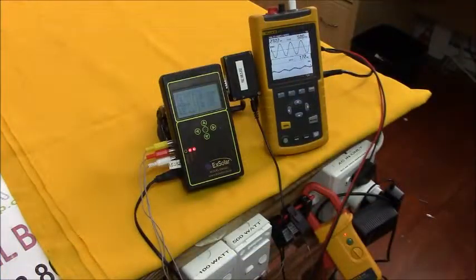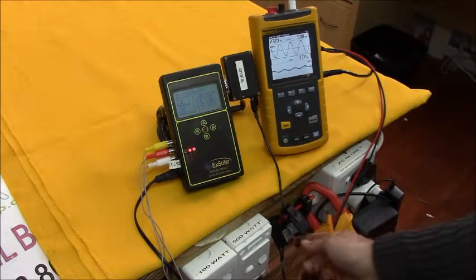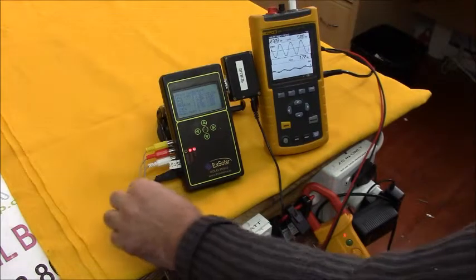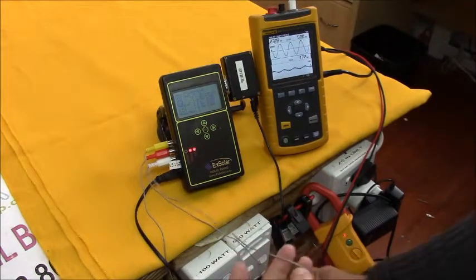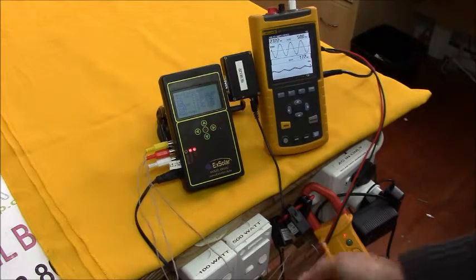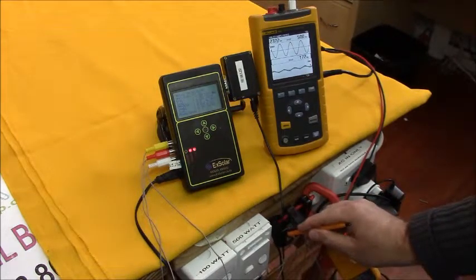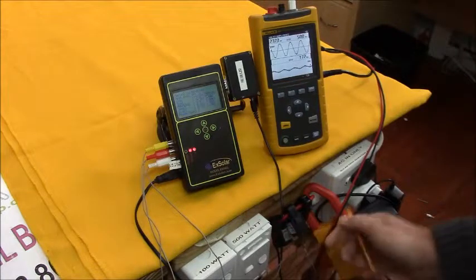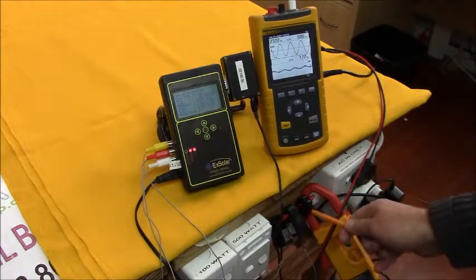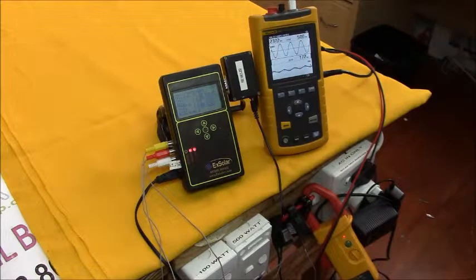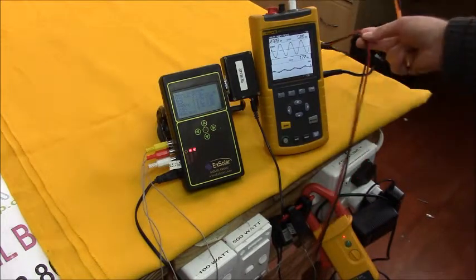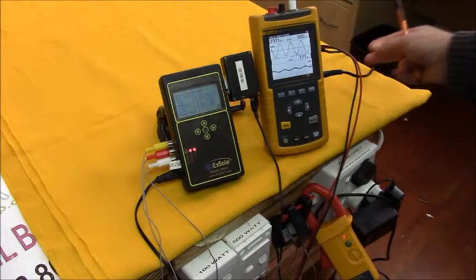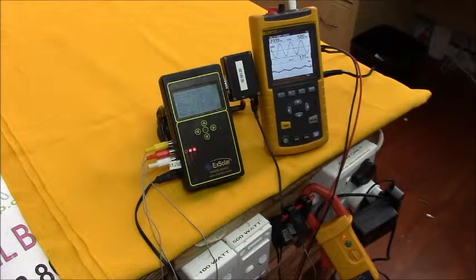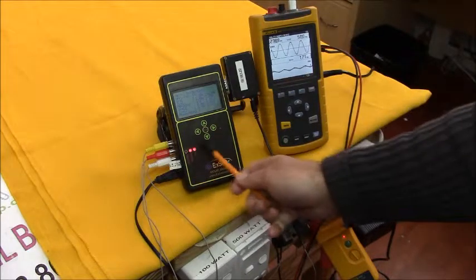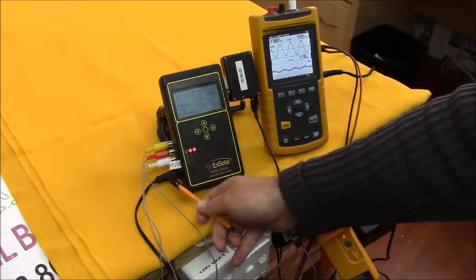Now we'll actually go into the calibration procedure of the energy monitor. And if you see here, we've got the sensors. The sensor that we're going to be using is sensor number 1 initially, which is this one here. We've checked it's fully closed, and it's on our load line. And we've also got the voltage sensors for the Fluke, which are stuck into the plug socket of the mains power supply. And on the energy monitor, that voltage is read at this position.